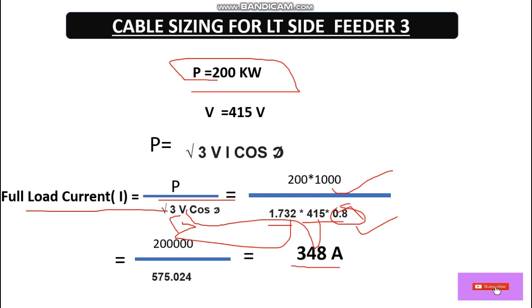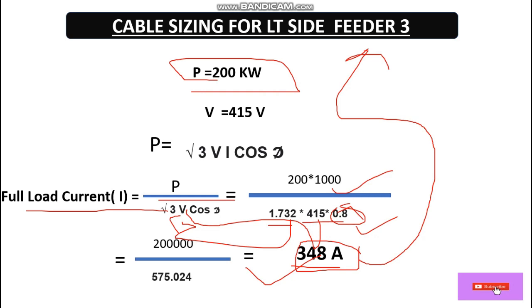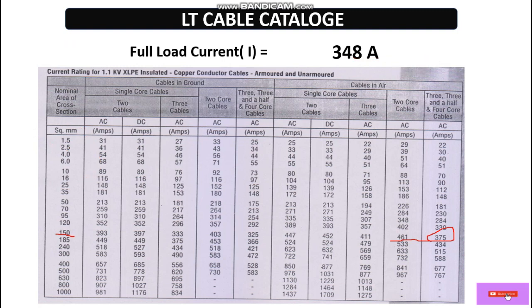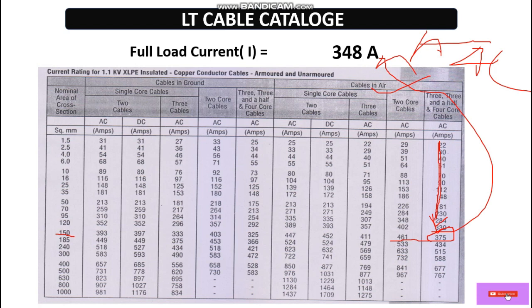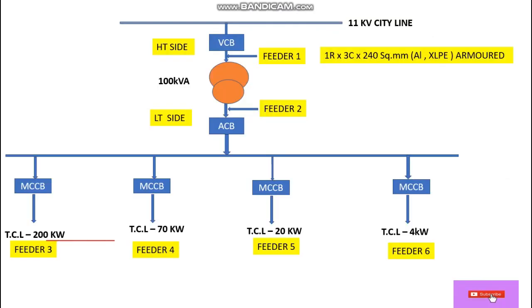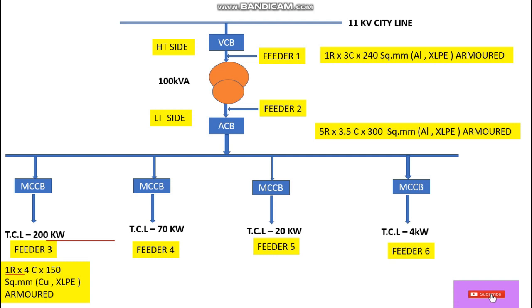According to this full load current of 348A, we look into the LT cable catalog to find the cable size. We are going for a four-core cable laid in air at ambient temperature. Looking at the catalog, 330A is under our load current, so we move to the higher value of 375A, which corresponds to a 150 sq mm cable. So for feeder three, the cable selected is one run, four-core, 150 sq mm copper XLPE insulated armored cable.